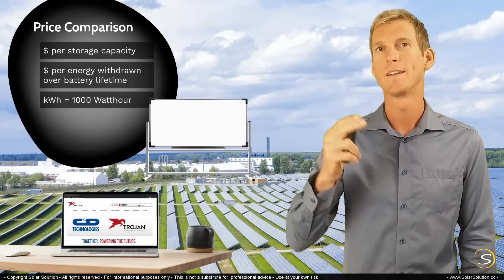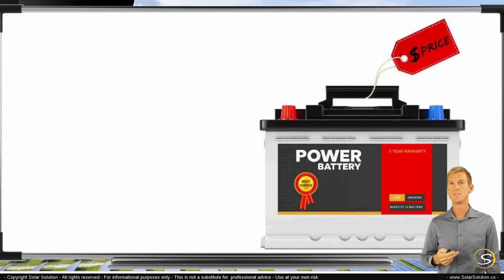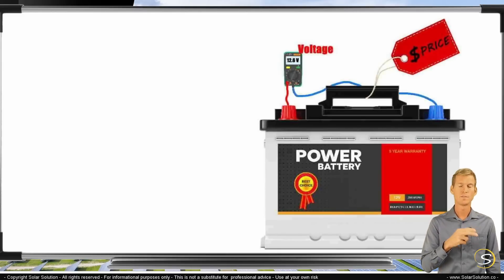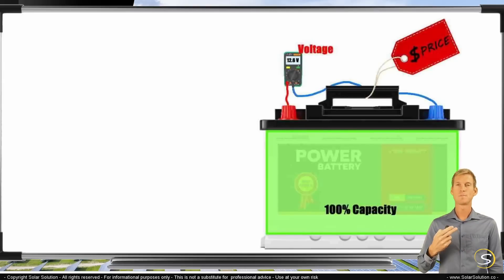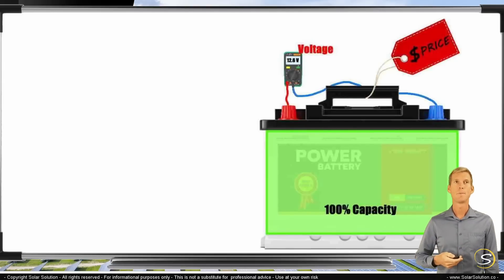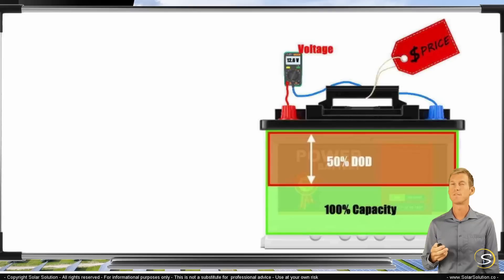Let's go to the whiteboard and start this comparison. We start with any battery which has an absolute purchase price — we use the US dollar here. The battery also has its own voltage: 2, 6, 12 volt, etc. It has its own absolute storage capacity, which is the 100% capacity. But we almost never use all of that capacity during normal operation. For lead acid batteries we normally only use around 50% maximum capacity, otherwise it would heavily impact the battery's lifetime.